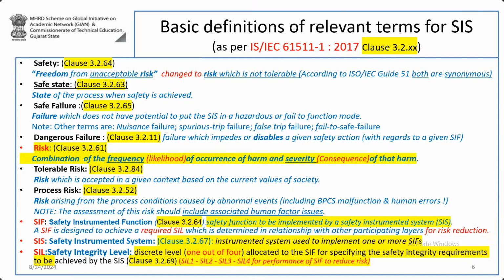Higher the risk, better performance is required by the safety system. The safety system is implemented for the safety functions, and safety functions are implemented by SIF, meaning safety instrumented functions. So every safety instrumented function needs to be specified: what level of performance you are requiring. That means if I'm SIL 1, I'll have some type of hardware, some type of architecture, some type of devices to be part of my instrumented function. So in short, each SIF has a specified SIL. There is no SIF without SIL.